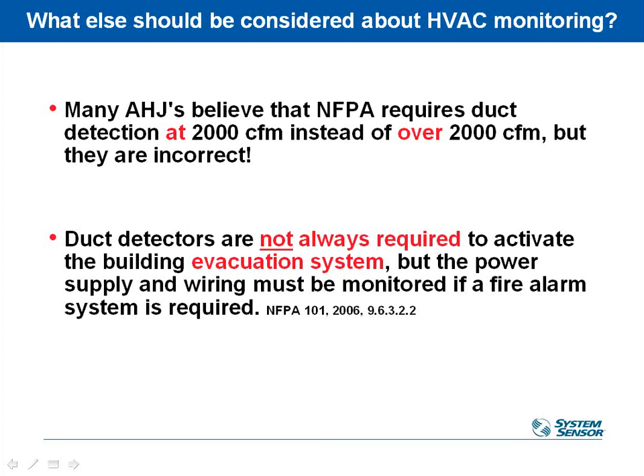Duct smoke detectors are not always required to activate the building evacuation system. So if you have space detectors in the space, those obviously alert the system, sound the horns, tell people to get out of there. The duct detector doesn't always have to integrate to that. Sometimes it does, sometimes it doesn't, and we'll talk about that.